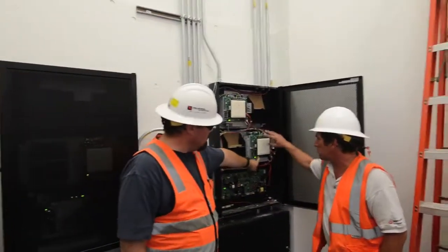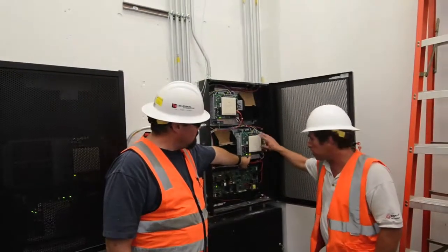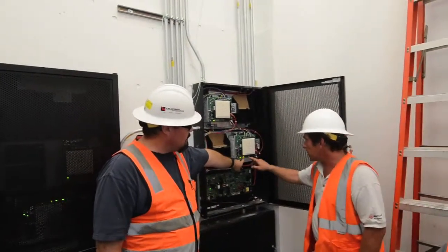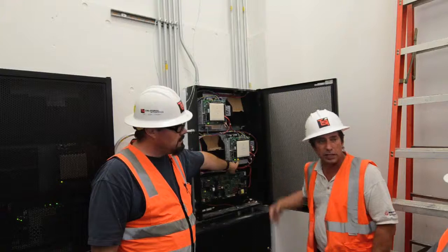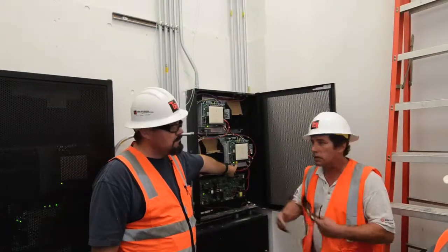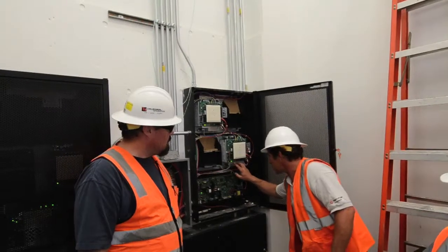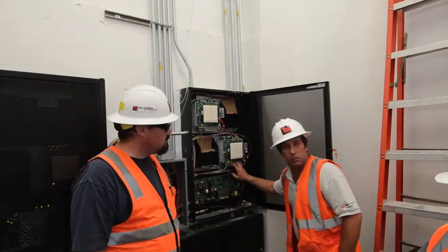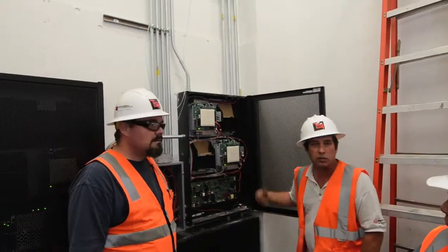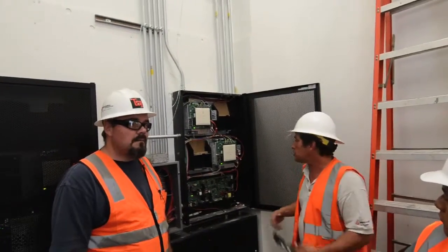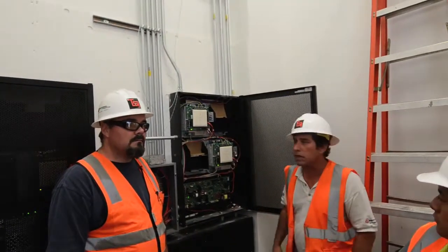There's 4 circuits located on this power supply. And that tells us that right there. We show up, it's clear, but we can see in the event log we've had a history of troubles on the power supply. Or we can come over here and see that circuit 3 was the circuit that had given us trouble in the past. It gives you something to look into and some direction as to where to go.